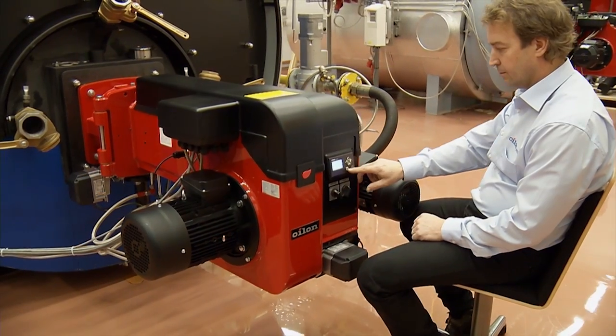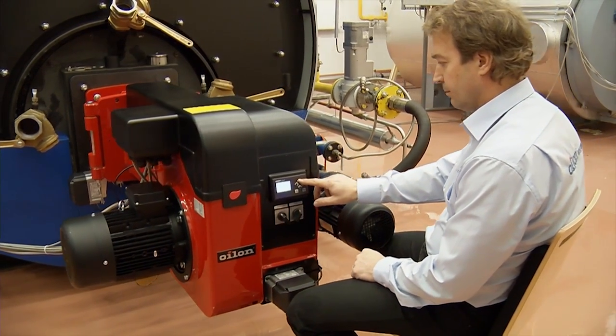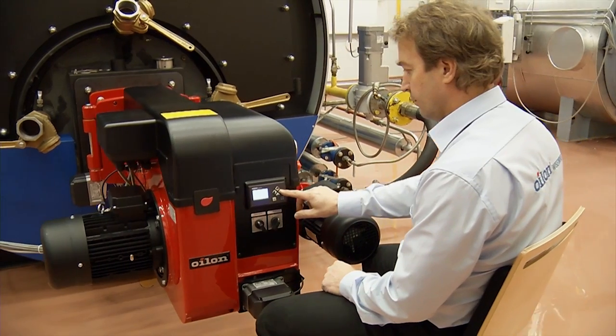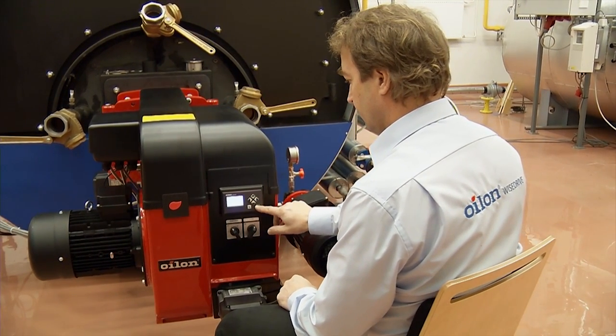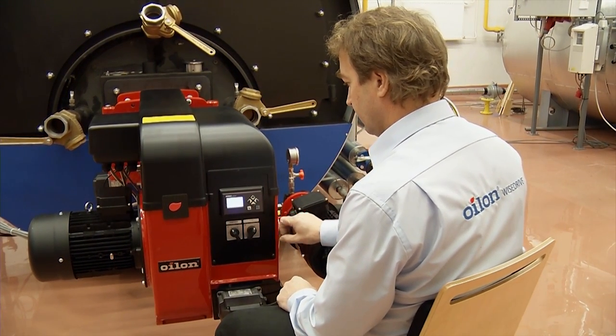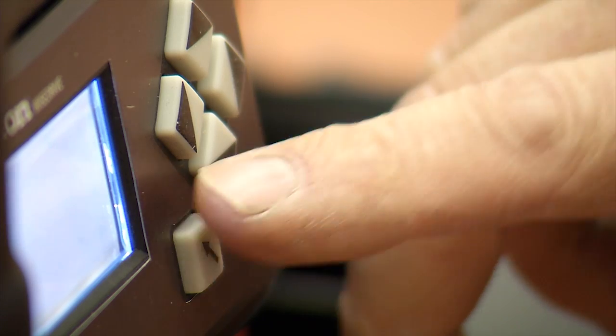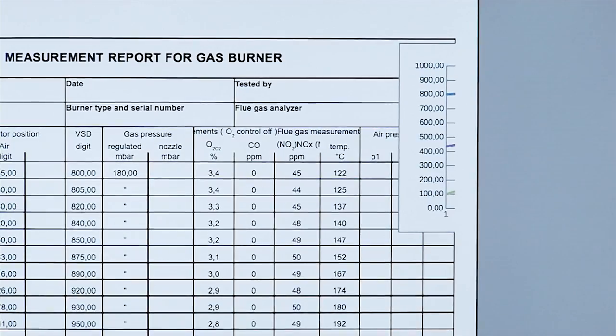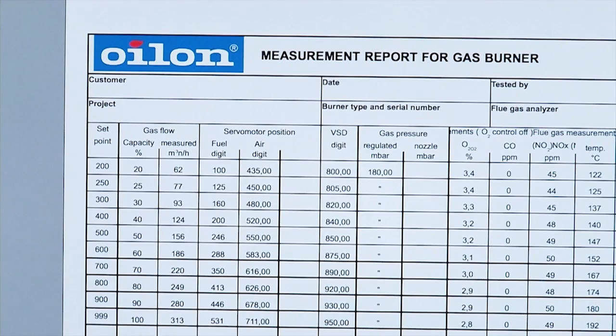The number of curve points is preset and cannot be changed. It is recommended to adjust all the preset points for the burner, because a complete curve will enhance the burner's performance significantly. Remember to fill in the measurement report for the burner.